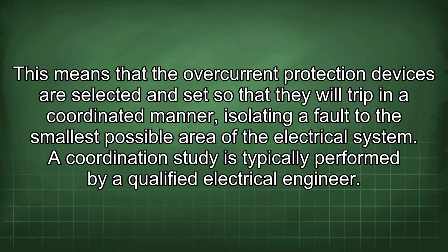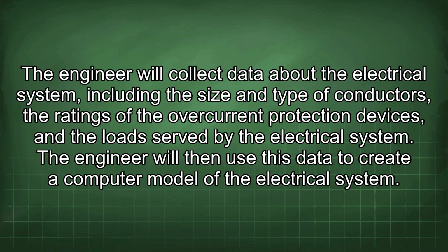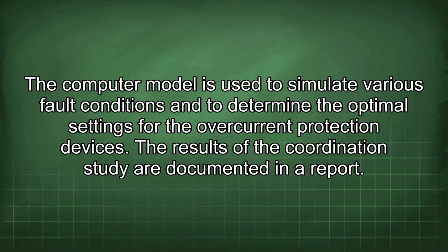A coordination study is typically performed by a qualified electrical engineer. The engineer will collect data about the electrical system, including the size and type of conductors, the ratings of the overcurrent protection devices, and the loads served by the electrical system. The engineer will then use this data to create a computer model of the electrical system. The computer model is used to simulate various fault conditions and to determine the optimal settings for the overcurrent protection devices. The results of the coordination study are documented in a report.